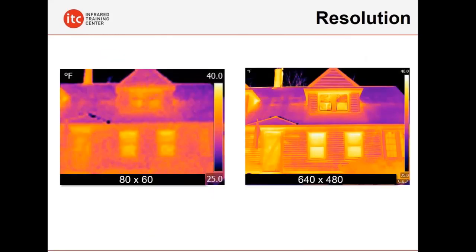Resolution is something we talk about as well. People are often attracted to the low price point, the lower cost thermal imagers because they're more affordable. Well, that affordability is also at a cost in the fact that you don't have as much resolution as perhaps a higher end camera. That could potentially cost you in your ability to be able to properly identify things like missing insulation or air leakage or perhaps electrical problems that are occurring in an outdoor utility situation, in a substation, things like that. You might miss these problems because you don't have sufficient resolution to be able to look at that problem.